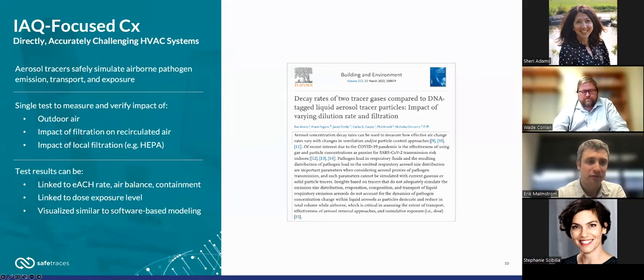The test results from this type of testing link to things like equivalent air change rates, air balance, and containment. We can express the data in more traditional engineering type metrics, but also in dose exposure levels, understanding the spectrum of risk based on how much particulate is in the air, putting that into a red, yellow, green relative risk spectrum to help people understand potential risk levels in certain spaces, and visualizing that data in an intuitive way using heat maps and things that help demystify air, airflow, and particulate levels.